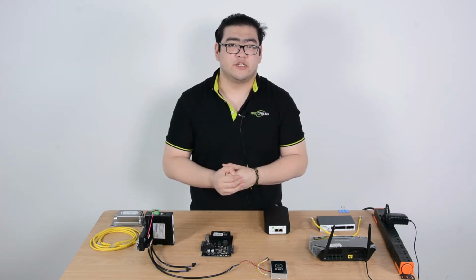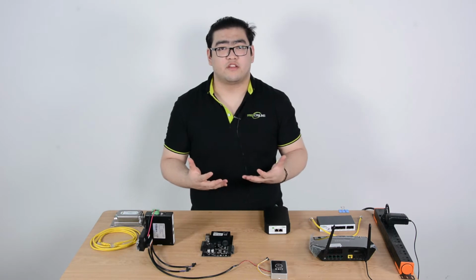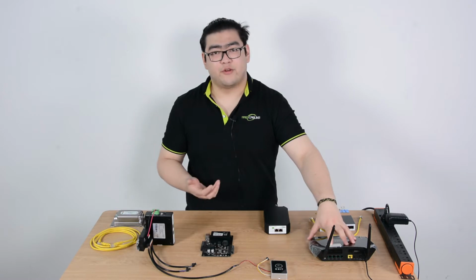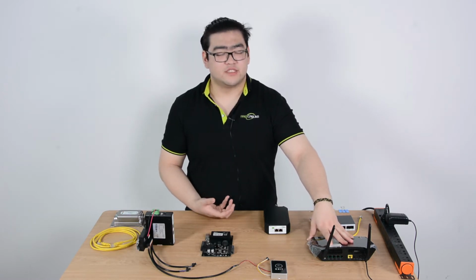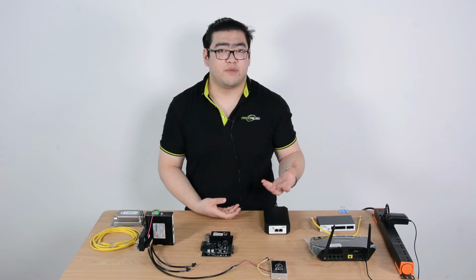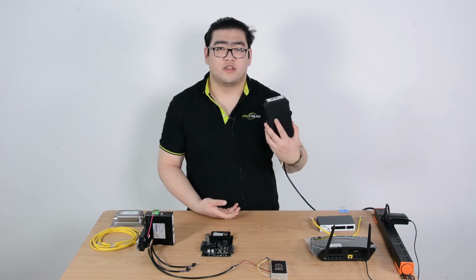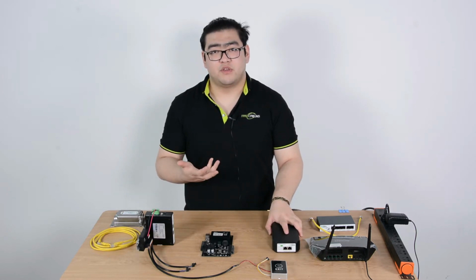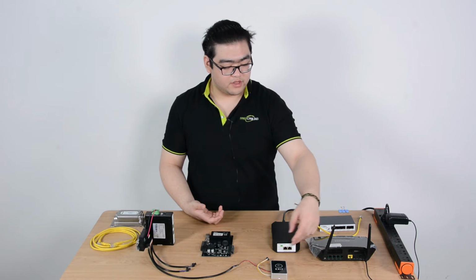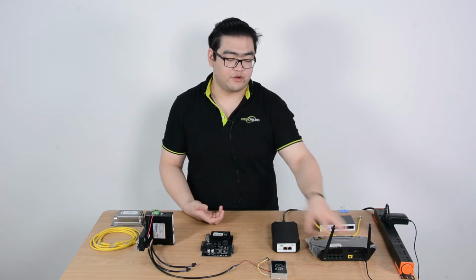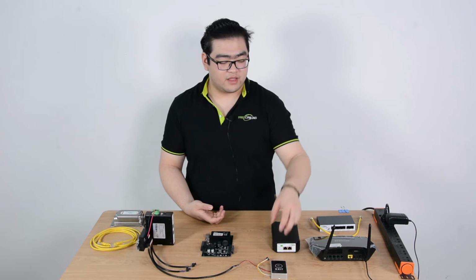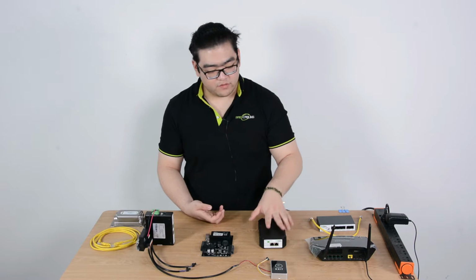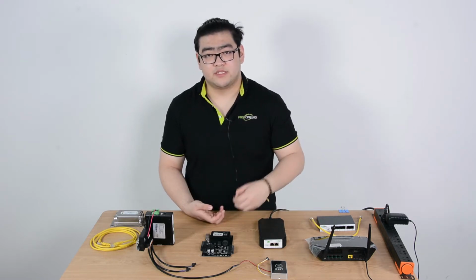So other than the PoE switch, a lot of people want to use PoE technology in their homes. And if we use it in our homes, we usually have a router. But a router is not a PoE device. It can help us exchange data, but it cannot provide power. In this case, we will use this 95 watts high power PoE injector. This will help us create PoE signals. The data will go through the Ethernet port right here when it connects to the router, and then it will be injected with power, and then at this port it will output PoE signals. So with these we can create a high power PoE system.